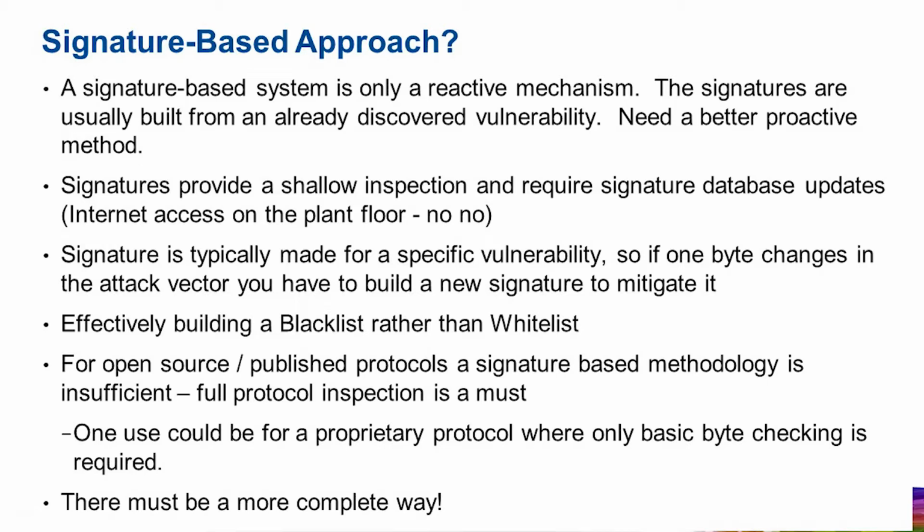In a lot of cases, signatures are only as good as what your signature database contains. And in addition, you're essentially building a blacklist rather than a whitelist. Someone's going to change one byte value or maybe one offset. Oh, we need to get a new signature. So it's this constant iterative process where you're just trying to build up this big blacklist. It's not really practical in the ICS world. Maybe in the IT world, it makes more sense. And obviously you don't want an internet connection from your plant out to the world to be getting these signatures back to your device.